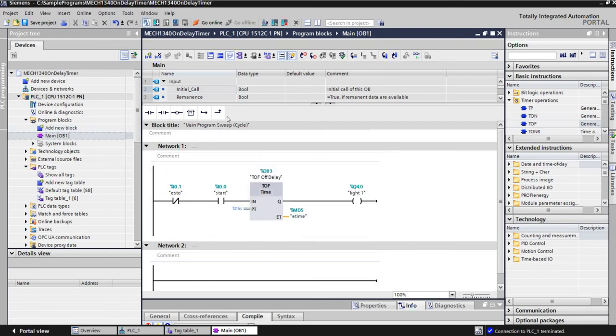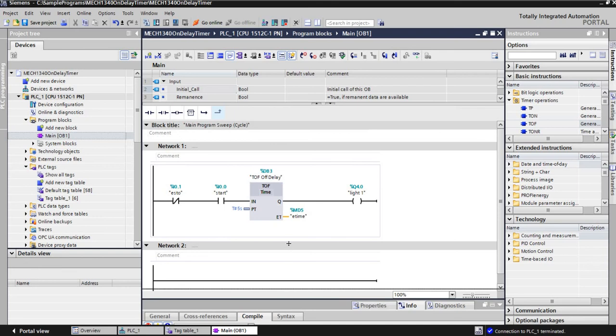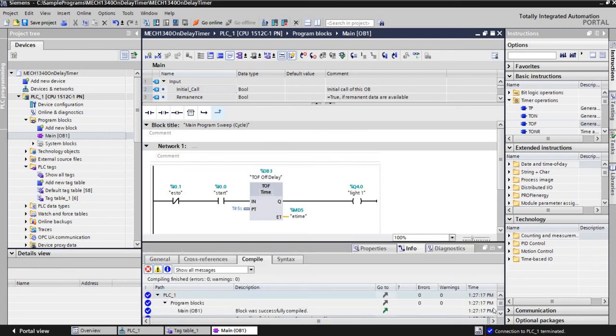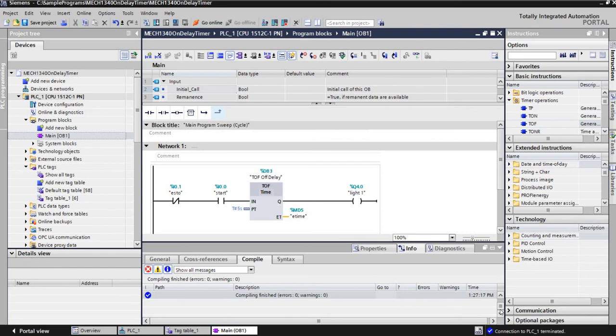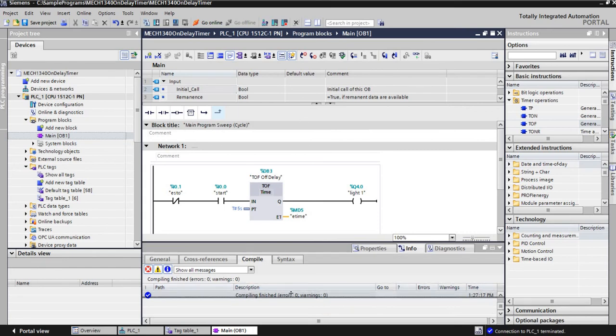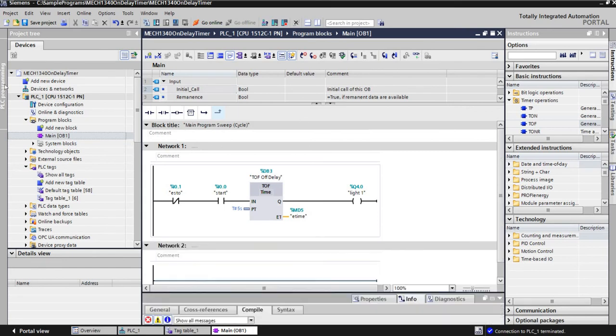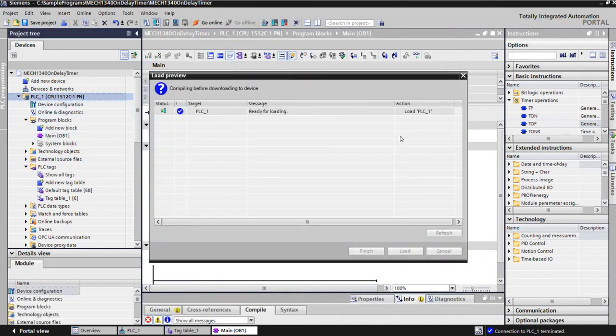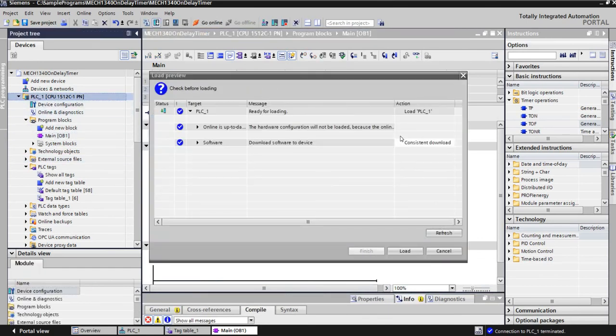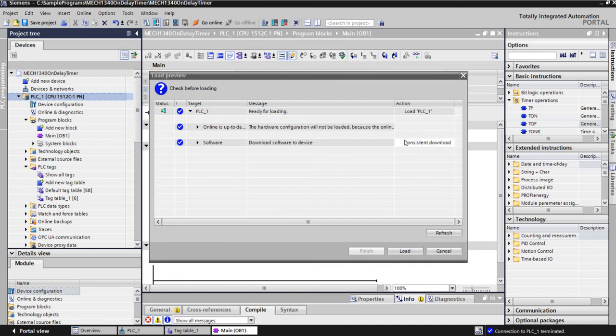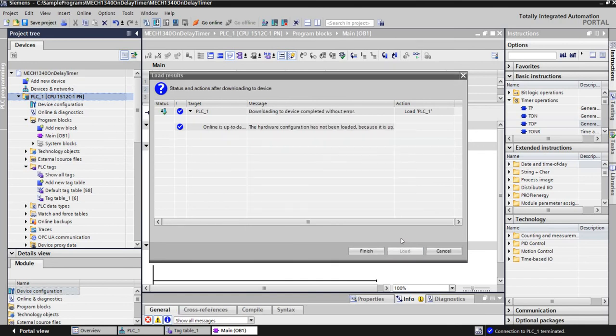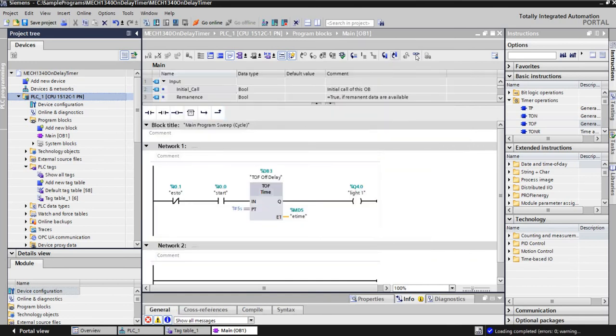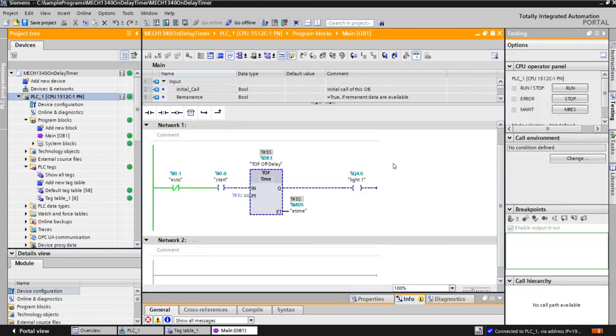Make sure that you compile right here. Make sure that there's no errors or warnings that you need to take a look at. So if I go down here, zero errors, zero warnings, so that's good. Bring this back down to monitor it. I'm going to click on the PLC. I'm going to download this to the PLC. Remember, I've already set up the connection to the PLC, so I don't have to re-go through all those steps if I keep the PLC on and I'm continuing on with my interface. So I'm going to hit the load button here. It's going to load it to the PLC and then hit finish.